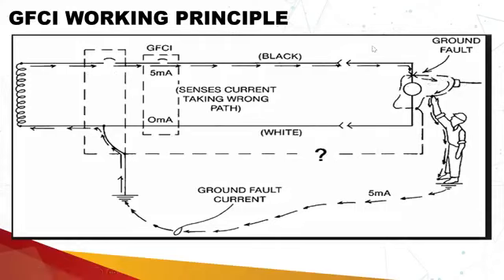When there is some internal fault in this equipment, the current will start to leak through this human body, and the return path will not see the exact amount of current which was entering into this equipment. So when there is a difference of 5 milliampere, 10 milliampere, whatever your setting is, that means that amount of current has started to pass through the human body and it is flowing into the ground. So when it senses that difference, it will operate and open the circuit.